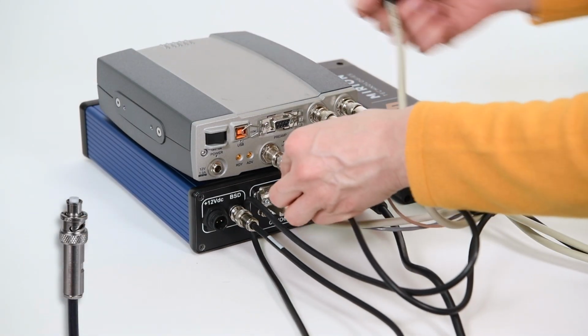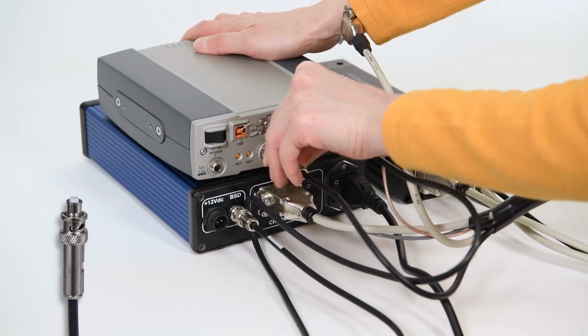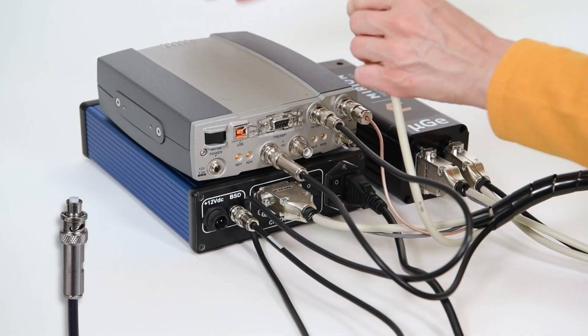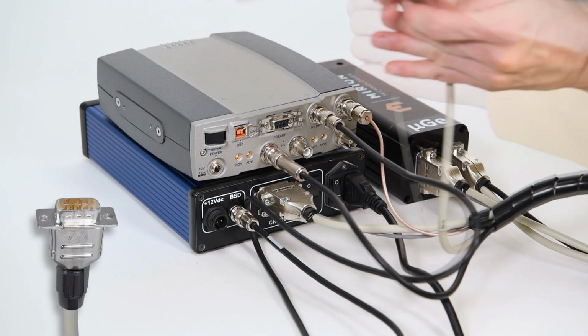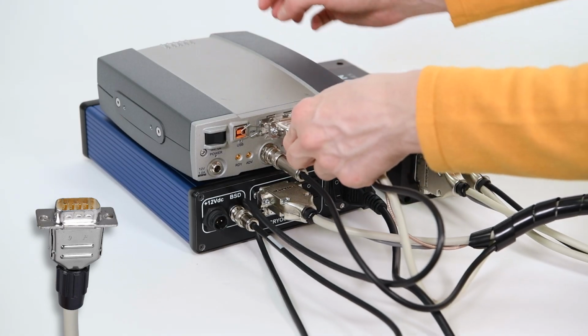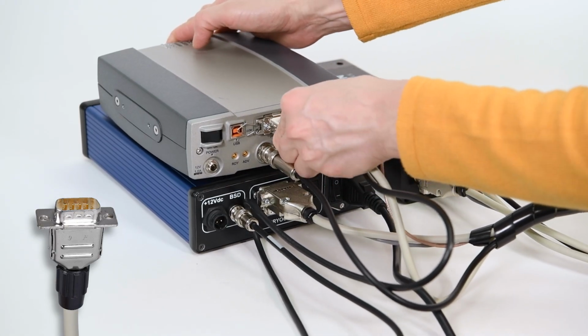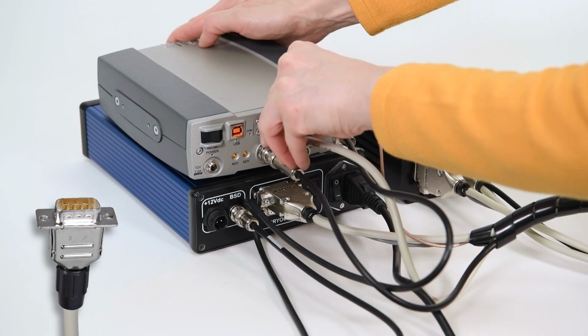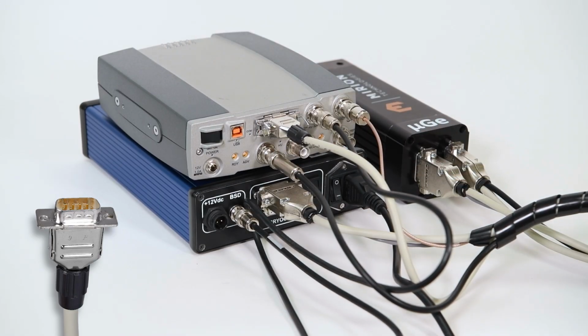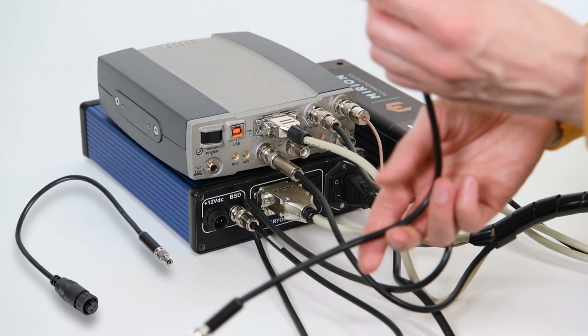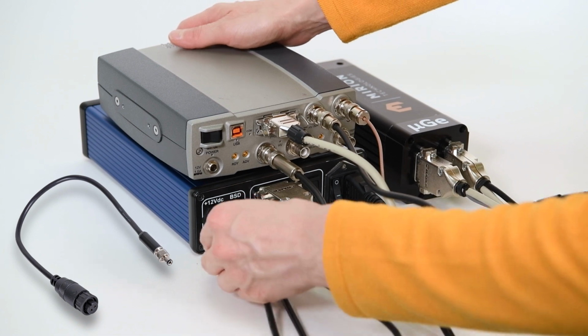Connect the high voltage cable. Ensure to check the spec sheet for the correct polarity of the high voltage. Connect the preamplifier cable to bias the detector. Connect the MCA power cable to the power supply.